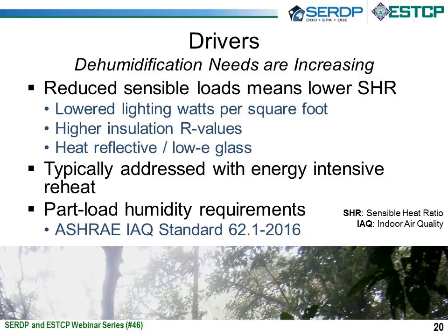It's really a split between sensible, which is temperature-related cooling, and dehumidification, which is latent cooling. So what's happening is that ratio has shifted over the past several years to where now dehumidification is becoming a bigger part of the cooling load. It's becoming more important. And what we're seeing in the field is that since these packaged DX air conditioners come with maybe a 70-30 or a 75-25 split, where 70% of the capacity is for cooling and 25% or 30% is for dehumidification, they're not able to meet the humidity loads, and we see a lot of reheat being used. And reheat's very energy intensive.